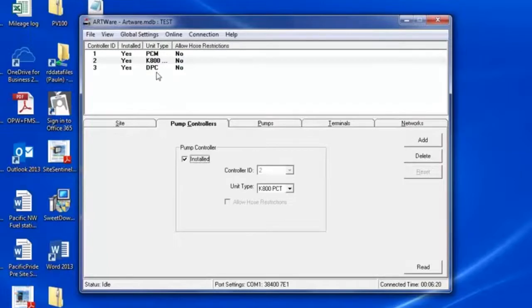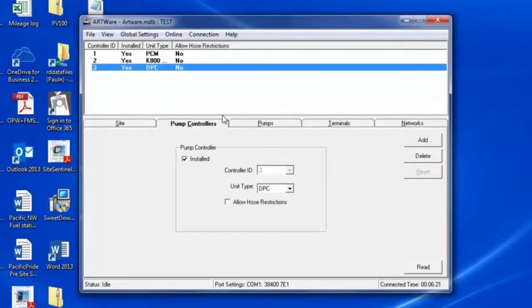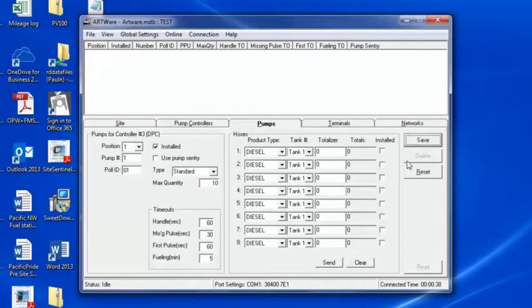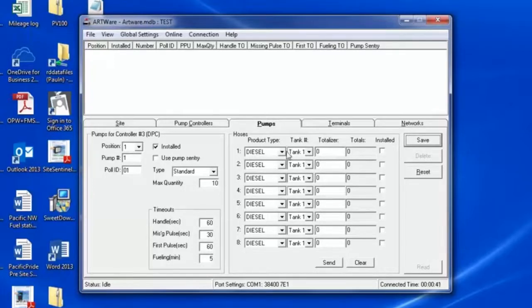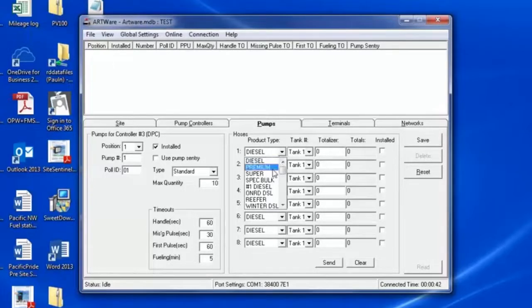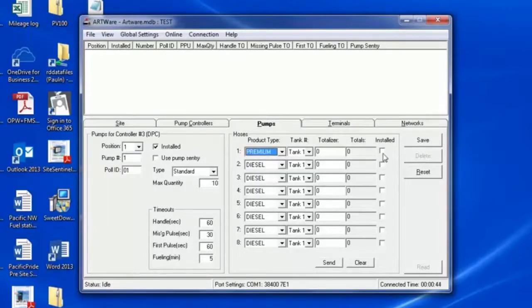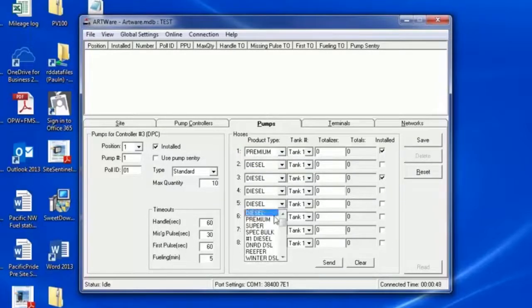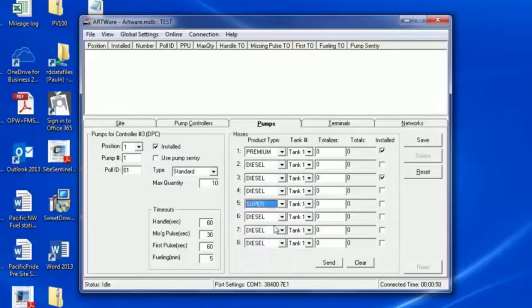Notice that selecting DPC and clicking Pumps shows 8 hoses. Click Add, then change your hoses to the corresponding product and make sure you click Install. If you do not click Add first, your setting changes will not save.